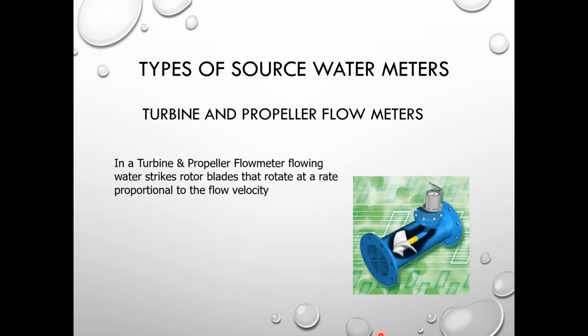So the most popular type for source water, again, is a turbine propeller meter. So water strikes the rotor blades and they rotate at a proportion of the velocity, right? The size range of these flow meters is 1 inch all the way up to 72 inches. Generally, your prop meters run at about 2% as far as accuracy.